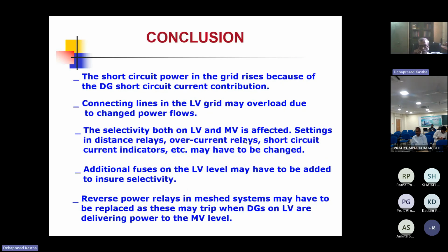Now, short circuit power in the grid rises because of the DG short circuit current contribution. Additional fuses on the LV may have to be added to ensure selectivity. Reverse power relays in the mesh system may have to be replaced, as they may trip when DGs on the LV are delivering power to the MV level. You cannot now say that the power is flowing only in one direction.